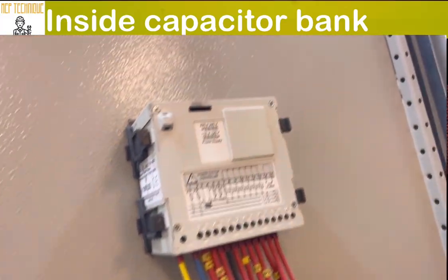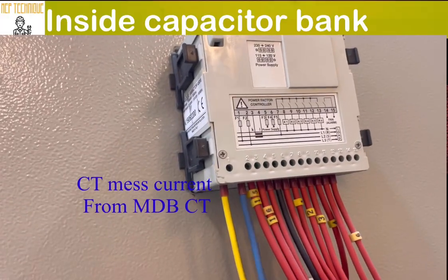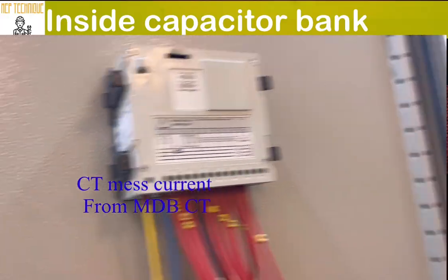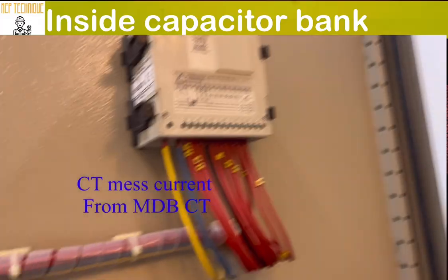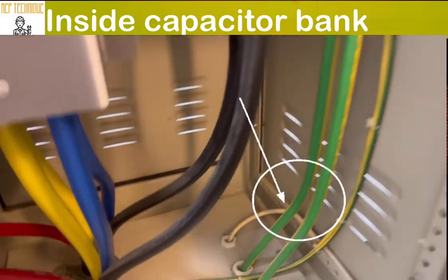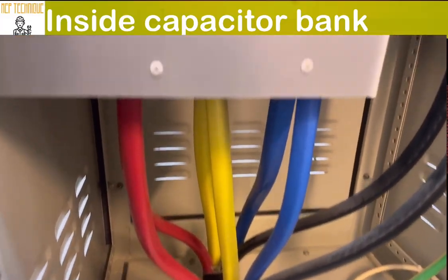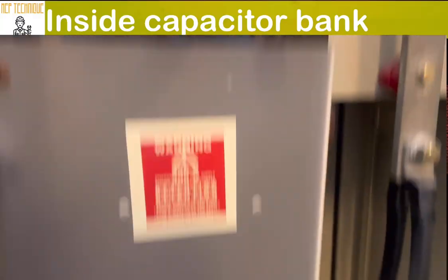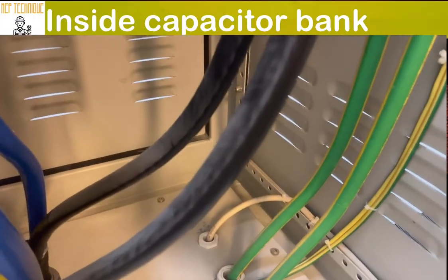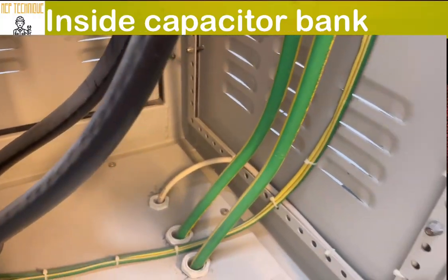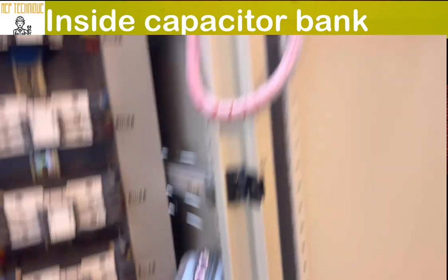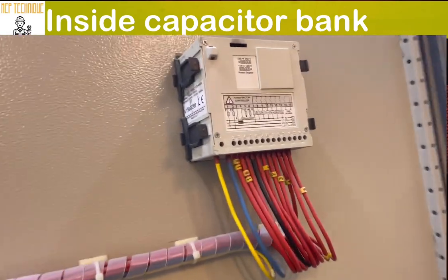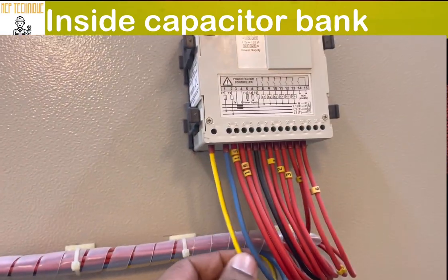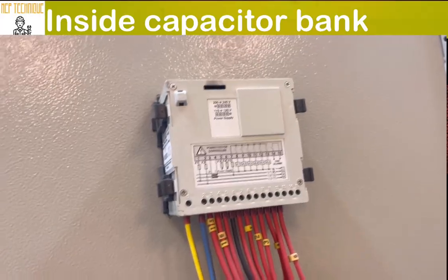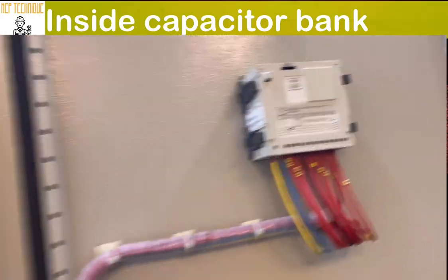That's why you can see there are two cables. This is carrying the CT measured current from the MDB. How it is carrying, I will show you. You can see these are the incoming cables, armored cable from the MDB. Then there is a white colored flexible cable, which is connected with our MDB CT, which is giving the command. When the load increases, more capacitors will be switched on. When the load decreases, fewer capacitors will be switched on.